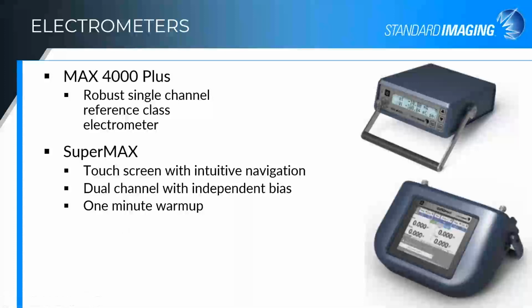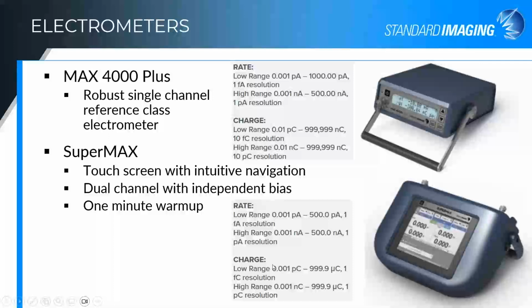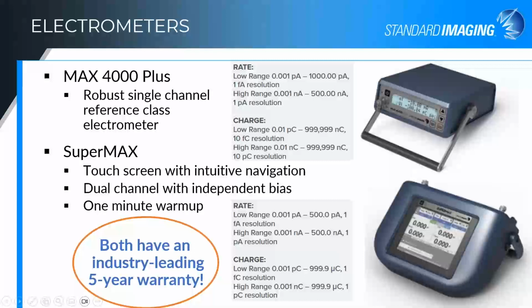I would be remiss if I didn't talk about electrometers. I know I've brought them up a bit. The two that we offer are the Max 4000 Plus, which is a very robust single channel reference class electrometer. The Super Max is the one that has the dual channels that you need if you have a W1 scintillator, and the touchscreen, faster warm up. In terms of specifications, the Supermax does a little bit better with the low range signal, but they both do excellently well in terms of long-term stability, lifetime calibratability, and ease of use. They also have an industry-leading 5-year warranty, which is, I like to say, an indication of how confident we are in the longevity of our products, that by default we stand behind them for 5 years.